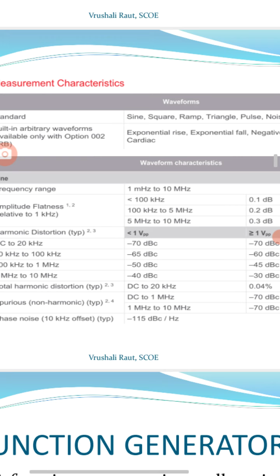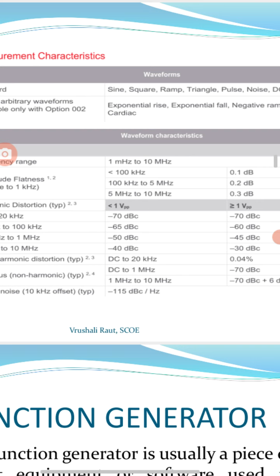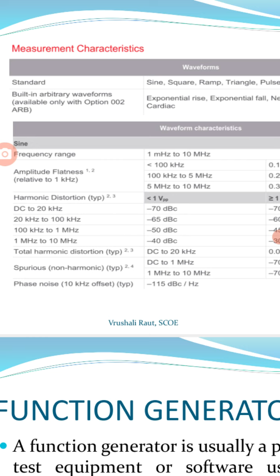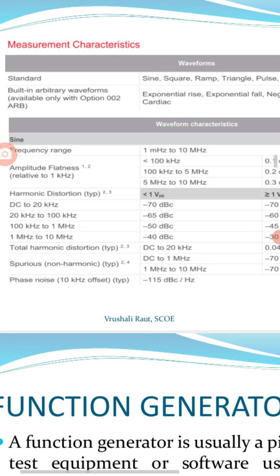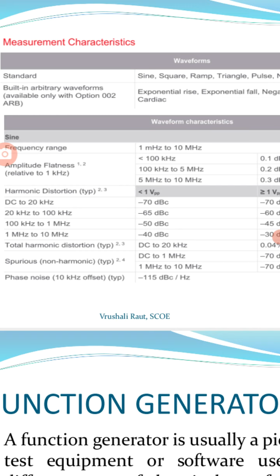Then the frequency range is 1 millihertz to 10 megahertz. Amplitude accuracy is 0.1 dB, 0.2 dB. Amplitude flatness, relative to 1 kilohertz, is up to 0.3 dB. Harmonic distortion for less than 1 volt peak to peak: DC to 20 kHz is minus 70 dB harmonic distortion, and others.